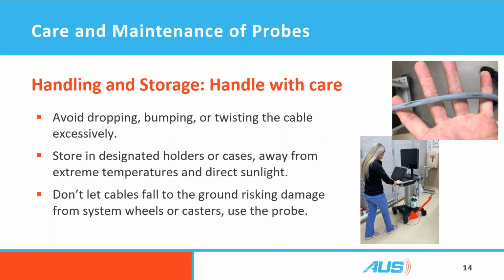I go over and I clean up the cables and I get it off the ground, and try to educate the sonographers how important it is, because it costs a lot of money. When they are not on the system, store them in designated holders and cases. And you don't want them out in sunshine. You don't want to leave them in your trunk if you're transporting them in super hot weather, direct sunlight. So just some things to think about when we're handling probes.